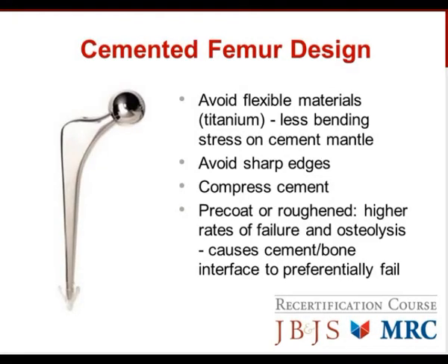Moving on to the cemented femur and implant design. When it comes to cemented implants, flexible materials have not performed as well. Titanium, for example, tends to be flexible, and it leads to bending stress on the cement mantle. This can result in cracking of the cement mantle and loosening. Avoiding sharp edges is important. Some of these tapered, smooth implants compress the cement and have a good long-term record.